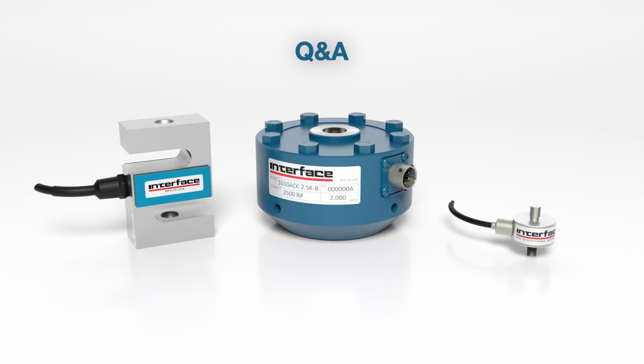What is the usable range of the load cell, and is it linear from 0 to 100%? That's a question we get asked quite a bit. The rule of thumb is typically 10% capacity, just because you're working with an adequate amount of signal strength that we aren't as concerned over some of the full-scale error influences such as temperature or other parameters.